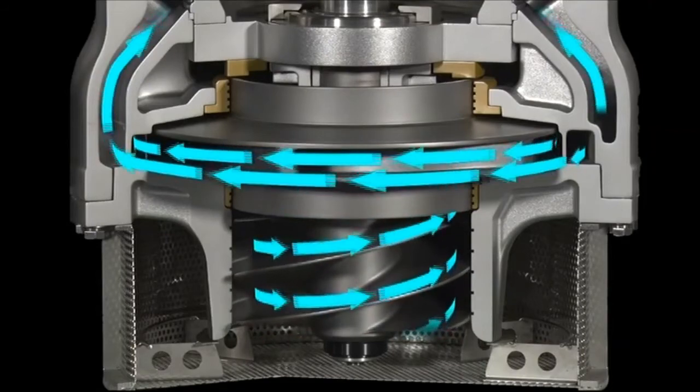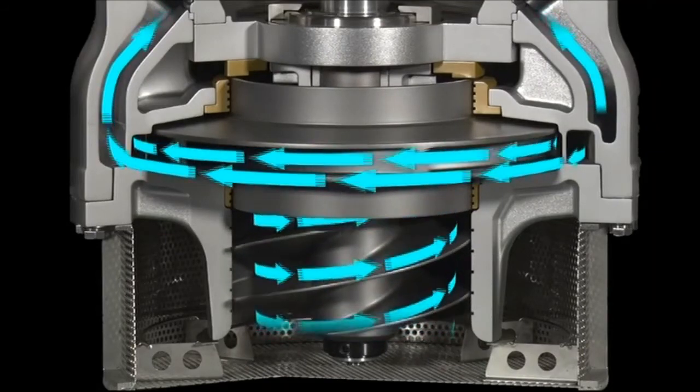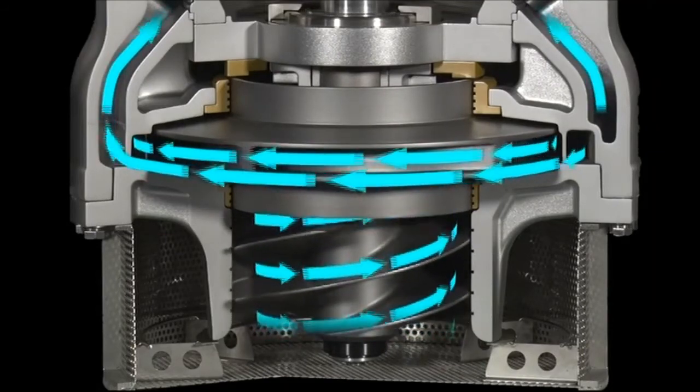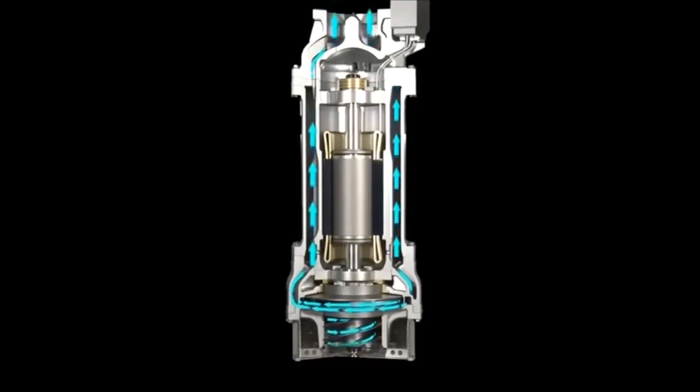LNG liquid is drawn into the impeller via the inducer located at the bottom of the pump. It then passes around the motor, goes through a check valve, and is discharged into the upper part of the pump.